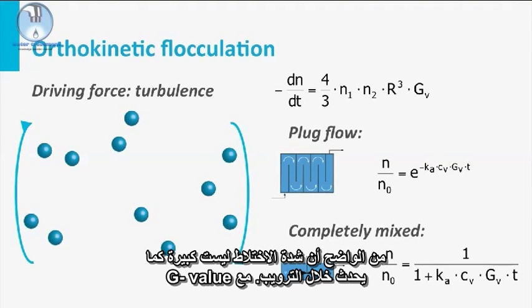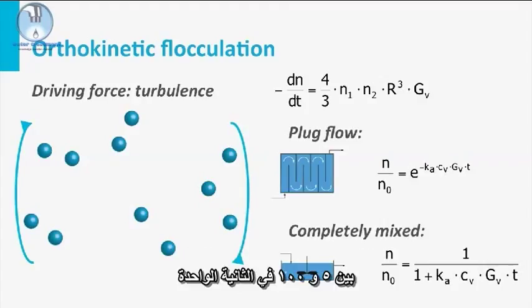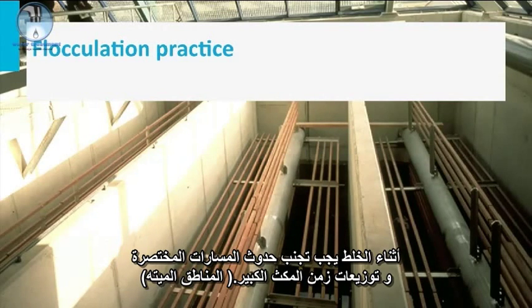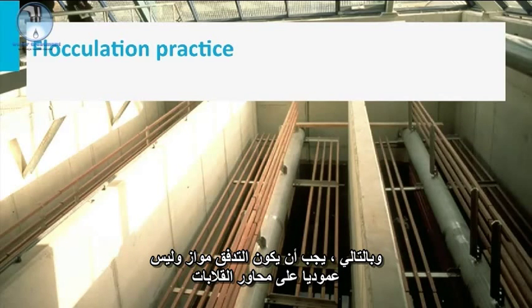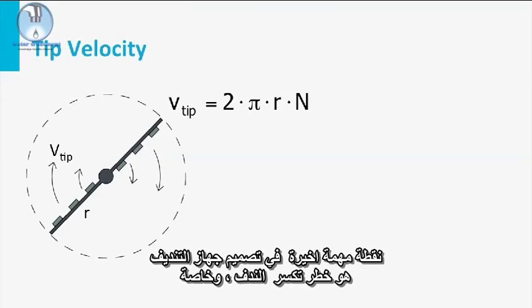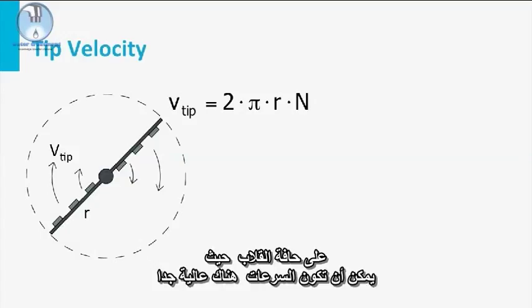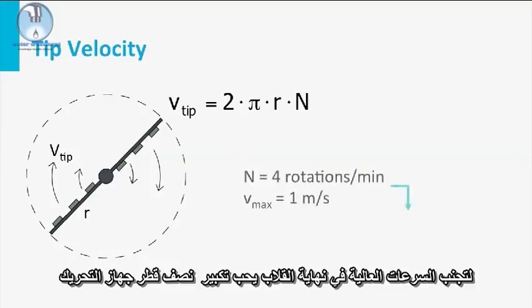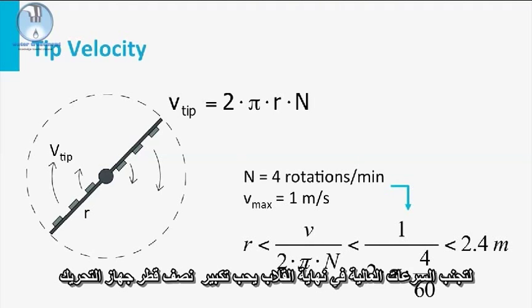Obviously, the mixing intensity is not as high as during coagulation, with G-values between 5 and 100 per second. In practice, mostly mechanical mixing is applied to be able to react to flow variations. During mixing, it is necessary to avoid short-circuiting and large residence time distributions. Therefore, the flow must be parallel and not perpendicular to the stirring axis. An important point for the design of a flocculation device is the risk of floc break-up, especially at the tips of the stirring devices where velocities can locally be very high. To avoid these high tip velocities, the radius of the stirring device should be limited.